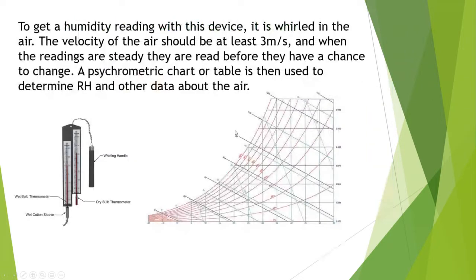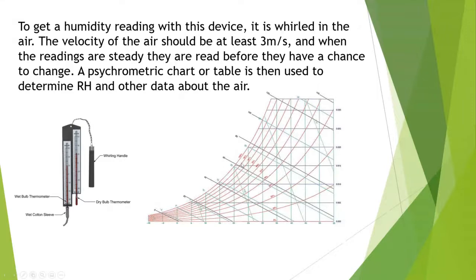To get a humidity reading, you swing the sling psychrometer through the air — the velocity should be at least three meters per second. When the readings are steady, you quickly read them. Then you apply the wet bulb and dry bulb temperatures to a psychrometric chart. The key insight: the higher the relative humidity, the less temperature difference between wet and dry bulbs; the lower the relative humidity, the greater the temperature difference. The water on the wet sock turning from liquid to vapor is called latent heat of vaporization.